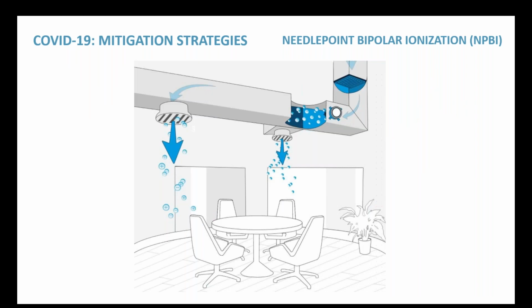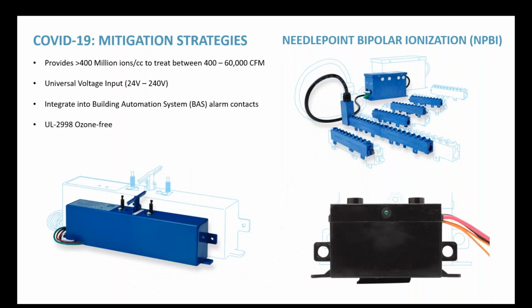There's a lot of different strategies for these, some of which are very similar to the UVC systems, with the one item of note when it comes to the bipolar ionization systems being that they tend to be put into the supply side, because the delivery of the bipolar ions is really meant to be directly to the space. There's a lot of different equipment that's out there, comes in various sizes. You will see manufacturers stating that it can be placed in an air handling unit at very large volumes, all the way down to fan coil systems, even residential furnace systems, things of that nature. So there's a wide variety of applications for this technology, as well as the UVC technology.